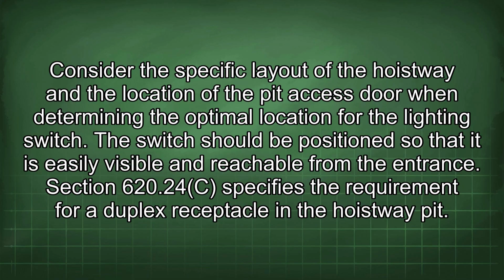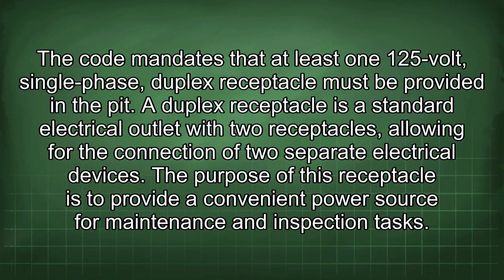Section 620.24c specifies the requirement for a duplex receptacle in the hoistway pit. The code mandates that at least one 125-volt single-phase duplex receptacle must be provided in the pit. A duplex receptacle is a standard electrical outlet with two receptacles, allowing for the connection of two separate electrical devices. The purpose of this receptacle is to provide a convenient power source for maintenance and inspection tasks.